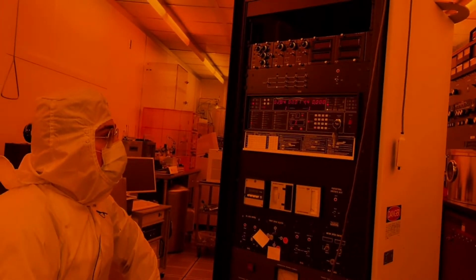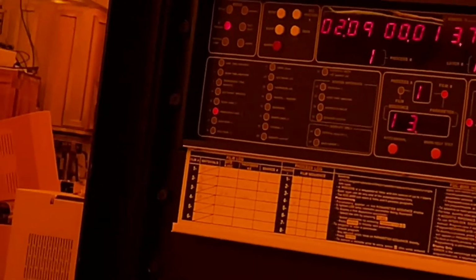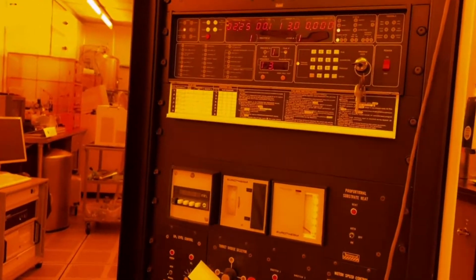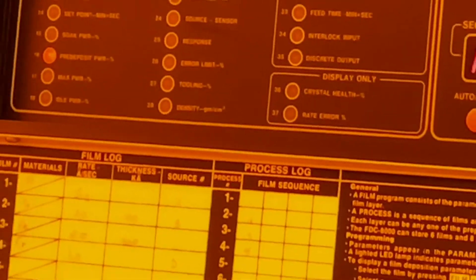So now it's reached the pre-deposit point. It's going to lower the power to 13%. During this time, we can see that our pressure restabilizes. And then it's going to sit in the pre-deposit state for another 30 seconds before it enters the deposit state. So at 2 minutes, 30 seconds, you'll be able to hear the shutter open. You see, since it's on auto, it is now open during the deposit state.